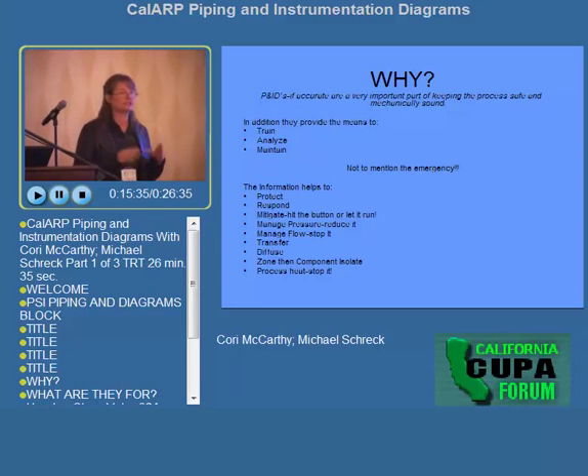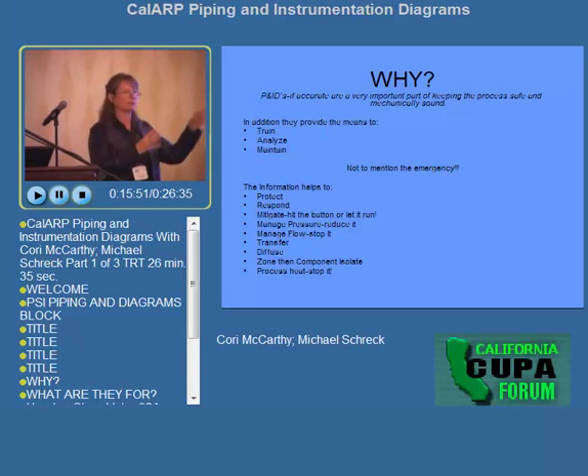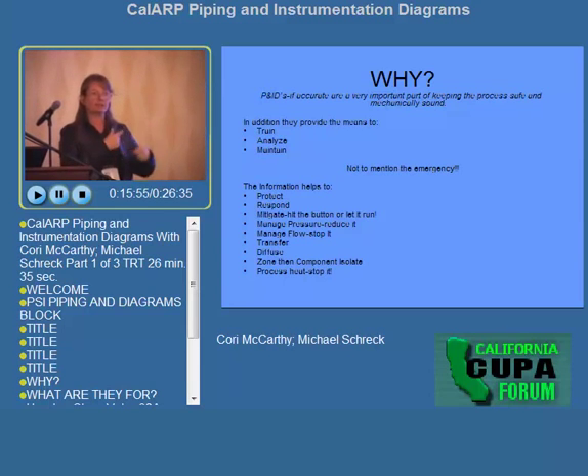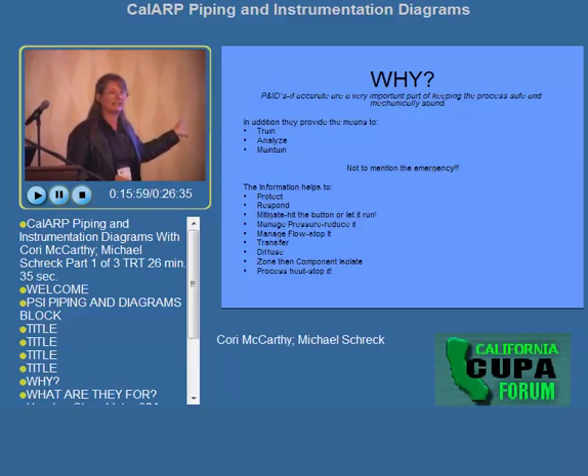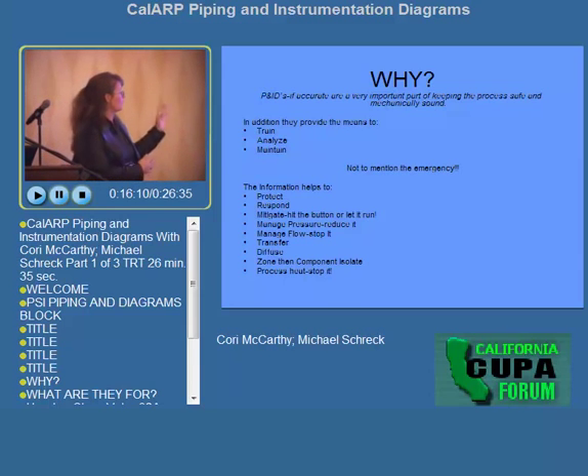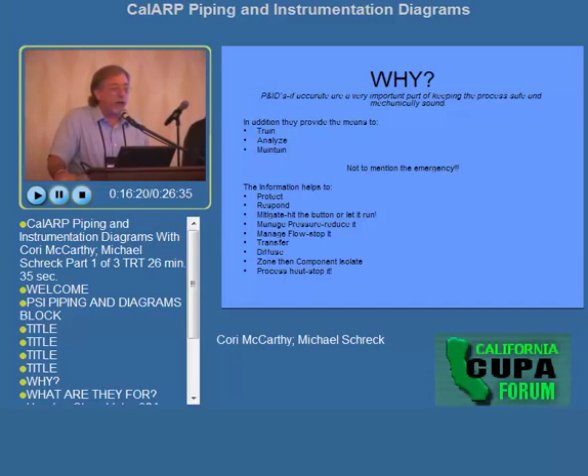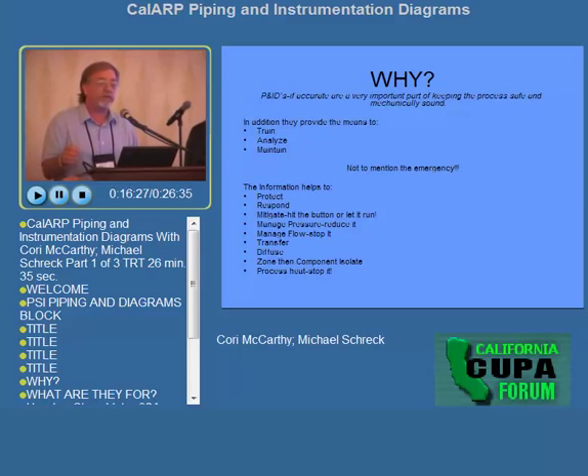Last but not least is process heat. If we have a process generating heat, there is the potential for continuing the release because of that heat — the process keeps running while everyone worries about the ammonia leak. The process generates the heat that the ammonia absorbs, requiring it to flash off 800 to 1,000 times expansion inside a component. With emergency response, it's very important that P&IDs are easy to read — color coding, standard symbols, flow direction — grouped with plot plans to create an effective tool for emergency responders.